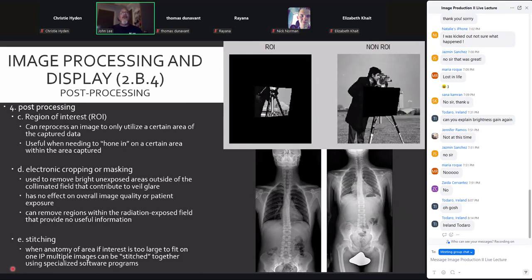Post-processing again with the region of interest. Say you have a lumbar spine, and it's just not looking great. You don't like the way the lookup table gave the contrast. Maybe the patient was large, so we've got a lot of grays in there. You can adjust the region of interest post-processing just around a specific area of tissue, and it will apply those values to the rest. It'll process the image over and it will change the scale of contrast.